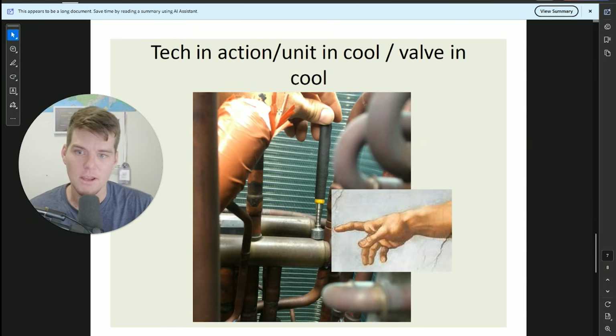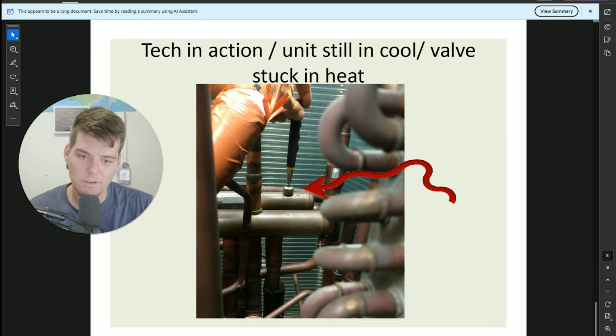So here's a live system, right? This is a unit in cooling, the valve is in cooling, and we can see it all the way to the far right here. This is the same thing, but the other valve, right, is stuck in heating mode. And why is that? Because the magnet doesn't get stuck until this portion of the valve, which again should be all the way to the right. This is how we determine, using a magnet, whether it's stuck on a four-way valve like this.